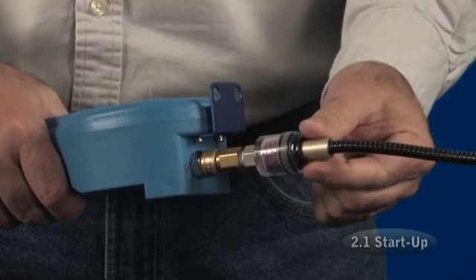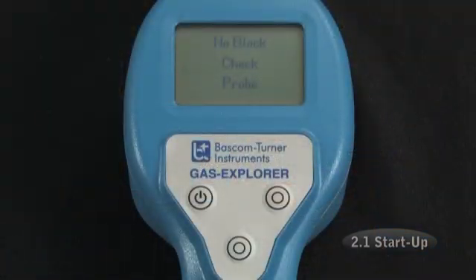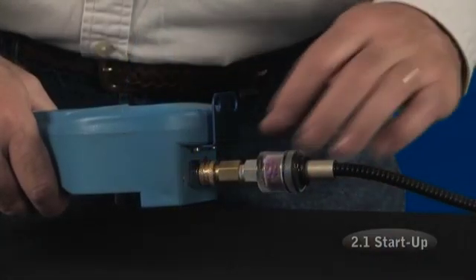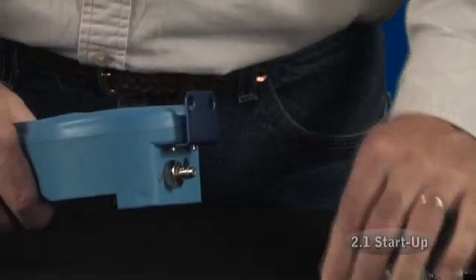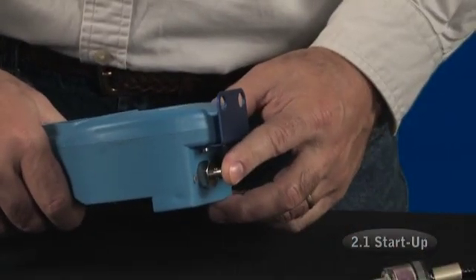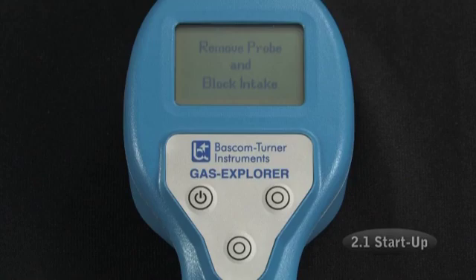If after another 30 seconds a block is still not detected, the Explorer will say, "Remove probe and block intake." In this case, disconnect the probe and filter and block the detector's input with your finger. If it still does not detect a block, it will say, "Repair pump," and automatically shut down.